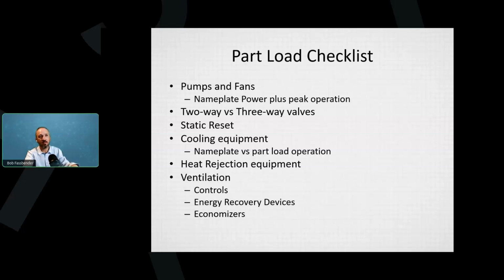Similar thing with fans if you have static reset. On cooling equipment, you want the type of equipment, and if you can find out how that equipment unloads, because some equipment unloads very well, like certain chillers, and that saves you more energy than the actual kW per ton. Heat rejection equipment, same deal. If it operates in conjunction with the cooling equipment, that's something you want to know.